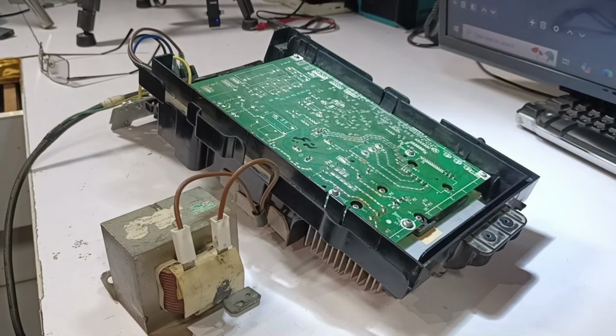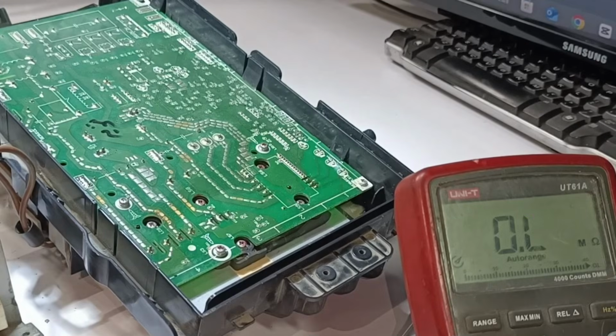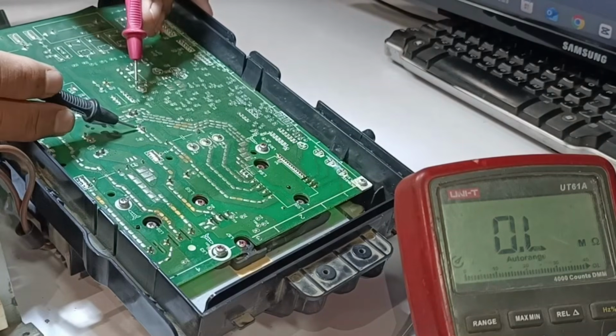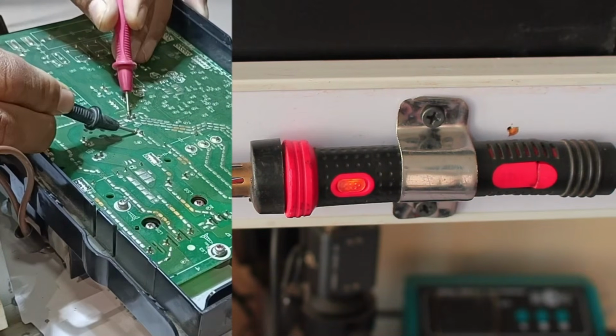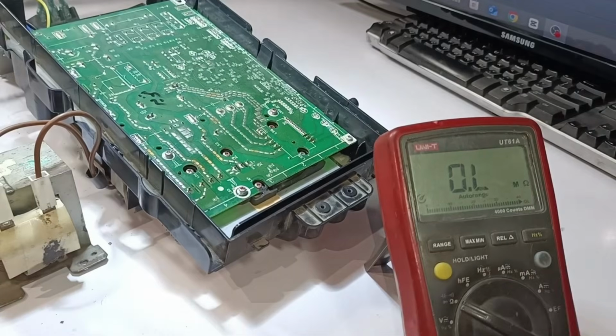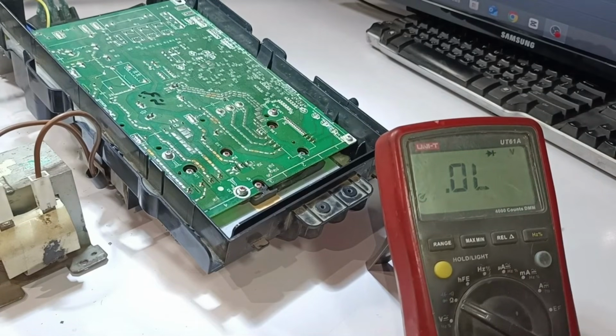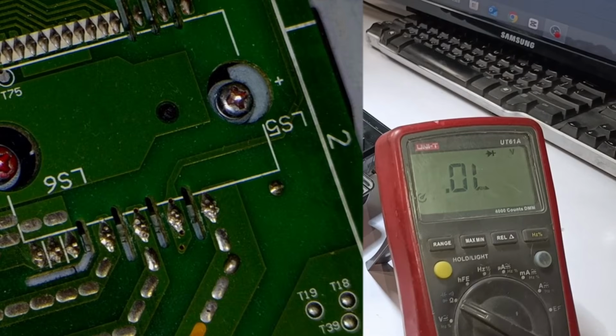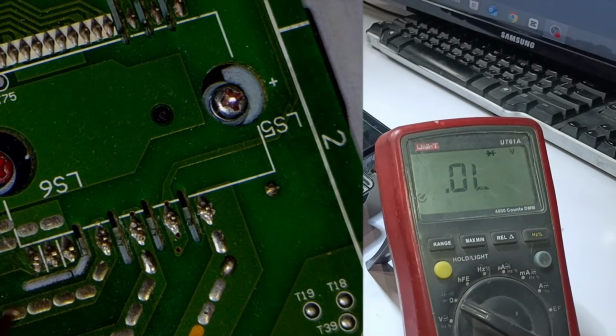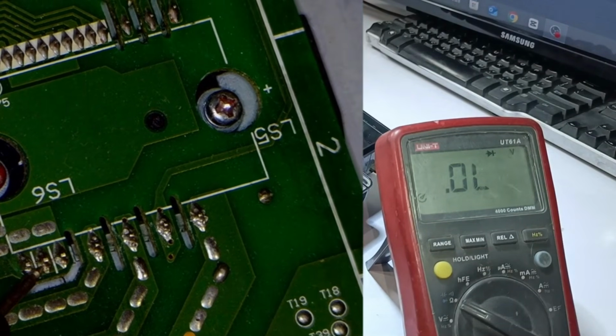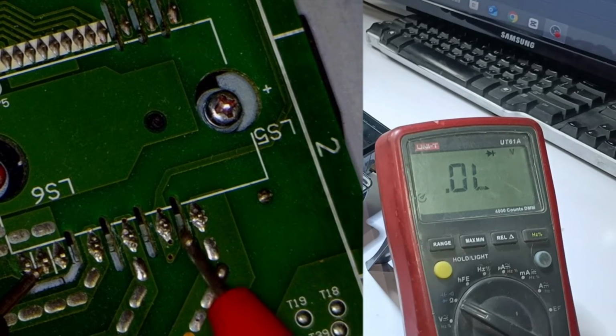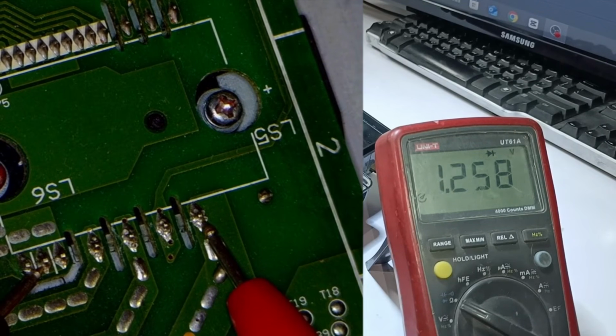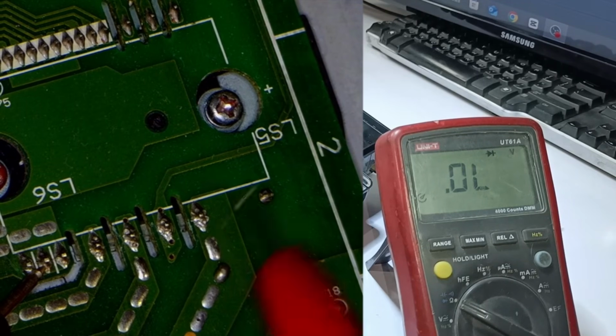Now, I'll disconnect the power supply and remove the switch for safety. Since we supplied direct power to the PCB, we will first discharge the capacitors. Using a resistive load, I have discharged the capacitors. Next, we set the multimeter to diode mode and started testing the IPM. We connected the negative probe to the negative terminal and the positive probe to the positive terminal of the IPM. Initially, there was some voltage drop, but then it stabilized and disappeared. In such a situation, there's a chance that the IPM is working fine.